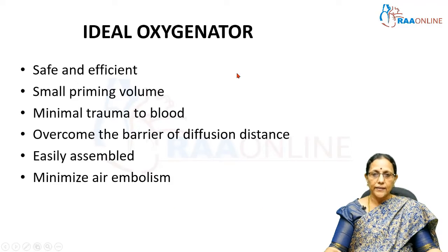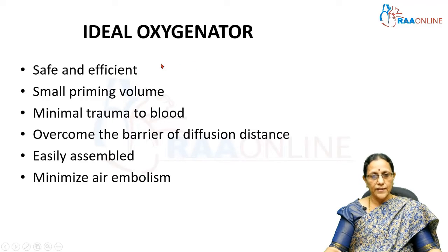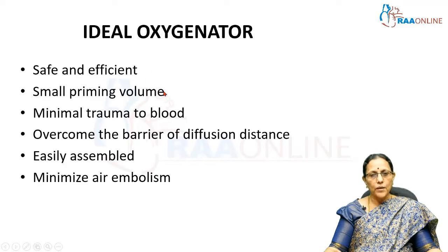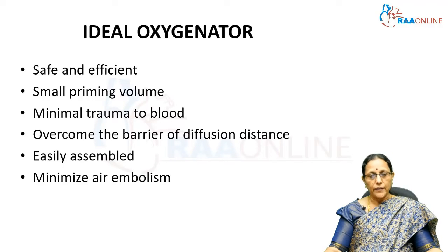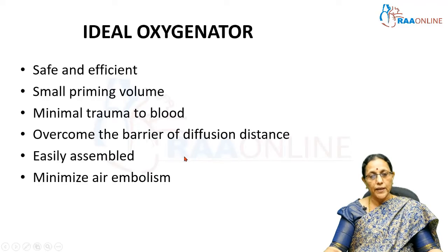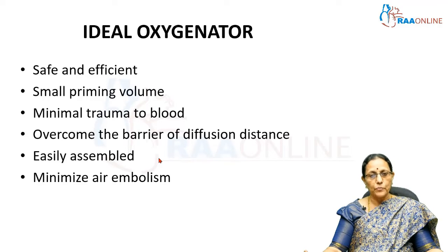What are the ideal characteristics of an oxygenator? First of all, it should be safe and efficient. It should have a considerably smaller priming volume so that there is minimum hemodilution of the patient. It should not create trauma to the blood, and it should overcome the barrier of diffusion distance — that is, the distance between the gas and the blood phase should be as minimum as possible. It should be assembled easily in case of emergencies and the hands-on work should be done with ease.